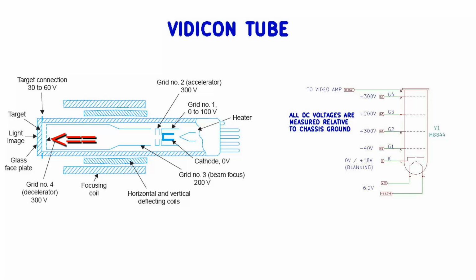The photoelectrode is called the target. When light strikes the photoconductor, it changes its electrical resistance. If there's a bright spot, more current flows out of the target connection, and if there's less light, then less current flows from that connection. That is how the image signal is generated as the electron beam spot is systematically swept over the imaging area by the horizontal and vertical deflection coils, and it is kept traveling in a straight line parallel to the axis of the tube by the action of the focusing coil.